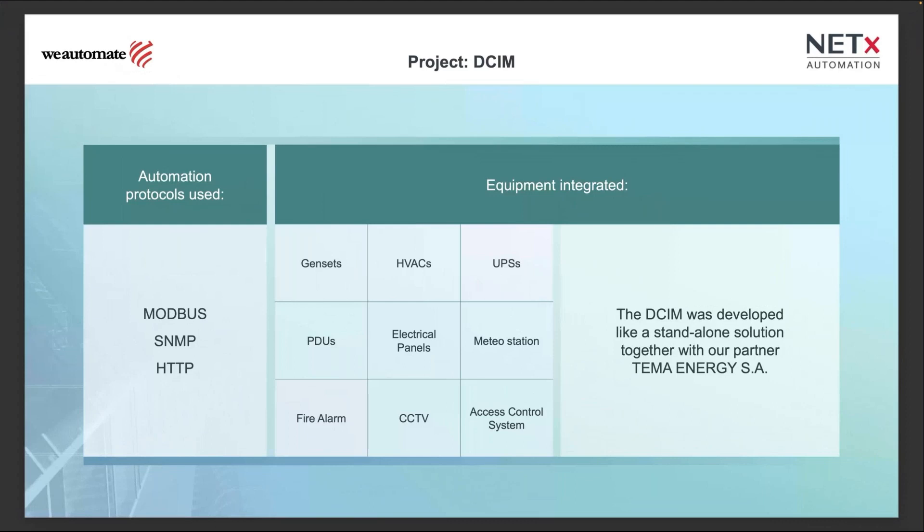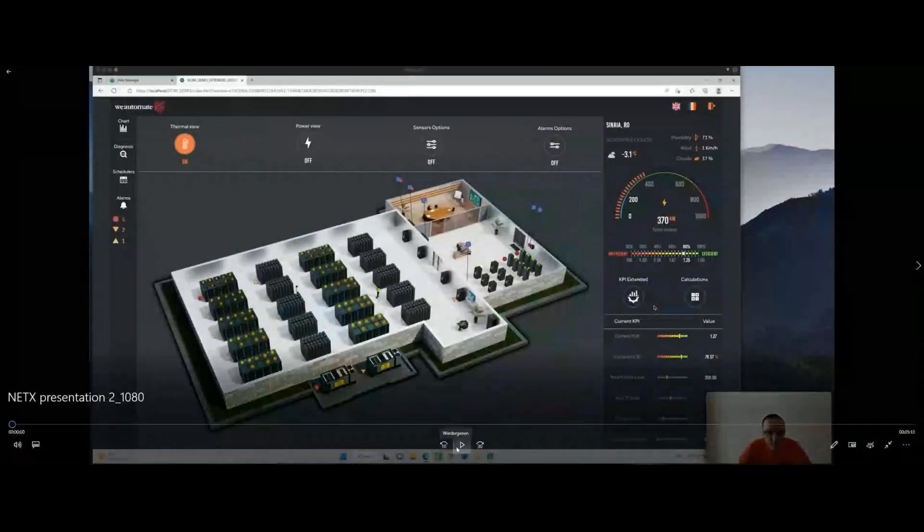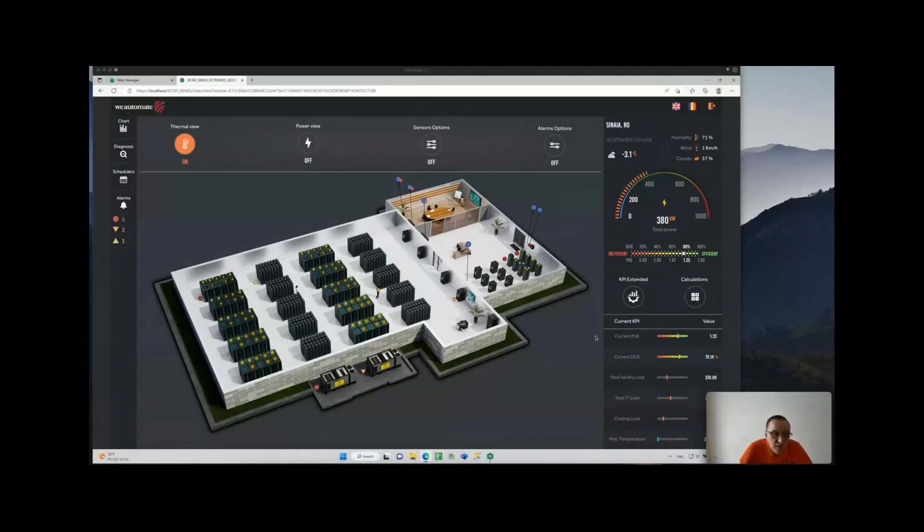We will now start the second part — the data center infrastructure management system video. Our DCIM product is built on the NETx BMS platform. It's a full-stack technology project — lights are controlled via KNX, UPSs and gensets via Modbus TCP and RTU, and many power distribution units and UPS systems are integrated via SNMP protocol.